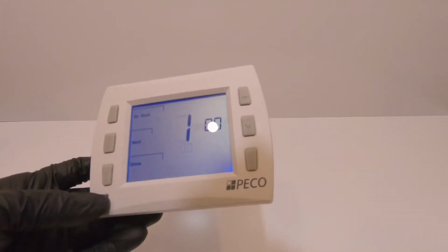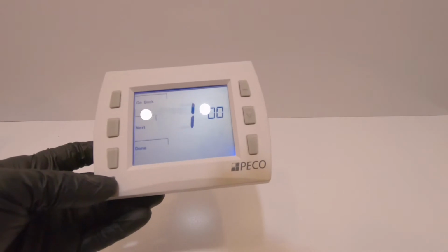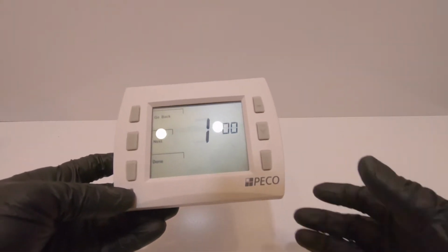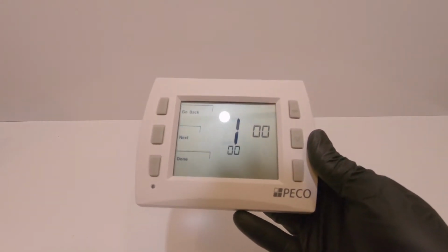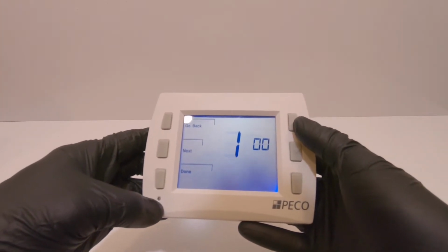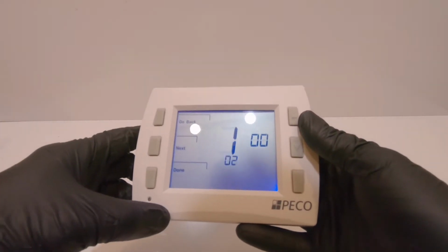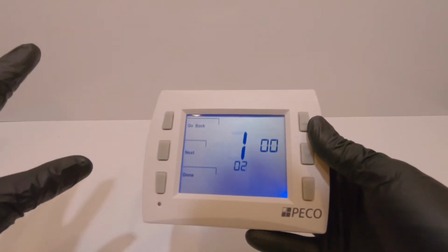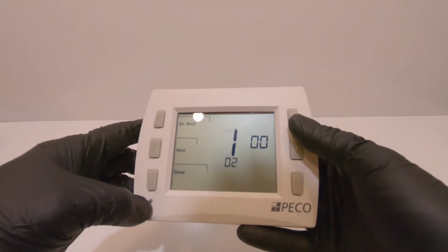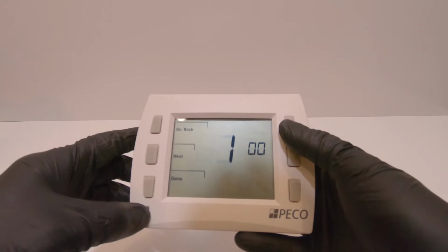That's going to allow somebody just to pretty much go up to the thermostat and turn it on and off, heat, cool, and whatever the temperature is. You also have setting 02, which is going to be a 5-1-1 schedule. So you have 5 days out of the week that you can schedule it, 1 day for Saturday and then 1 day for Sunday. And each of those are going to be different schedules.